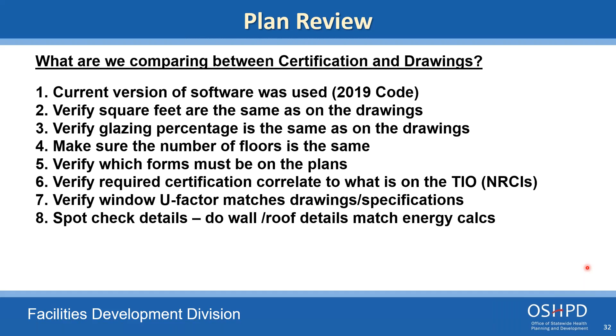What do we want to see on the plans? As mentioned, the NRCC forms stating compliance with the design must be on the plans. Typically these are in the mechanical drawings, but they can be wherever you want, as long as it's clear—whether grouped together or separated—so we're not wasting review time searching for documents, since they can sometimes be spread out pretty thin. What we want to see is that they're all grouped together. You can have energy document sheets where everything is pasted together. Typically we see them in the mechanical drawings since those are impacted a lot more.